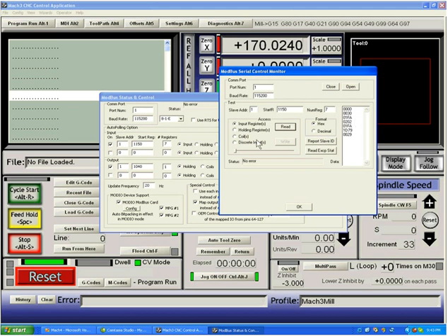Now you can also send data to a Modbus. We could, for example, here we type in the data that we're going to send to a Modbus device, and you can see I can just type a bunch of zeros or leave the random data. We're going to send to the holding registers starting at address 1040, which is the memory address of Peter's Mod I/O board on its output registers.